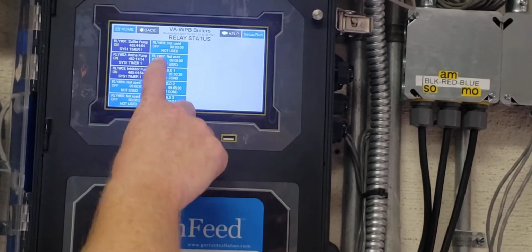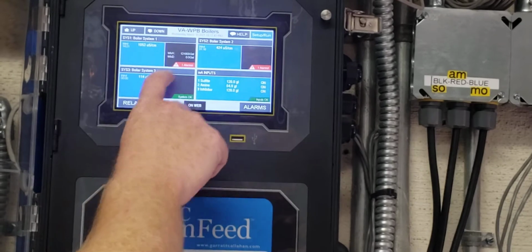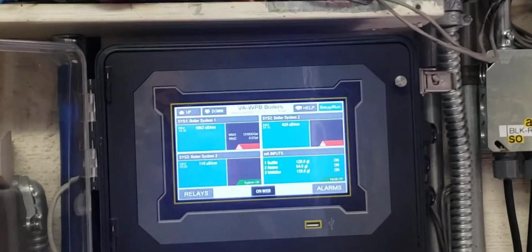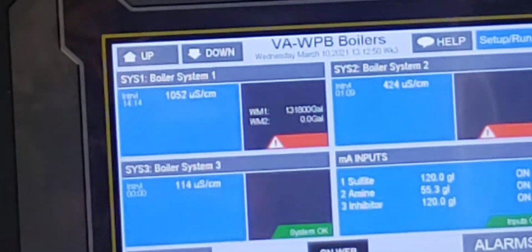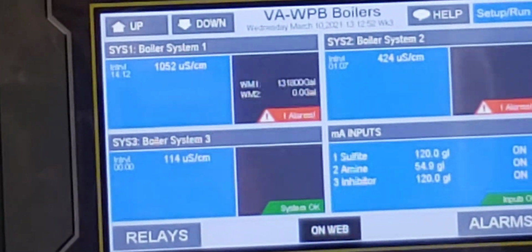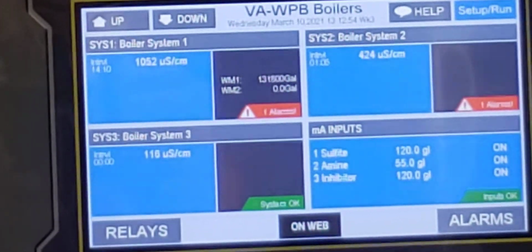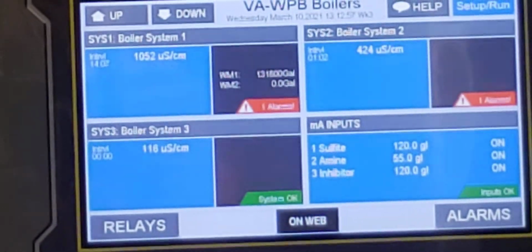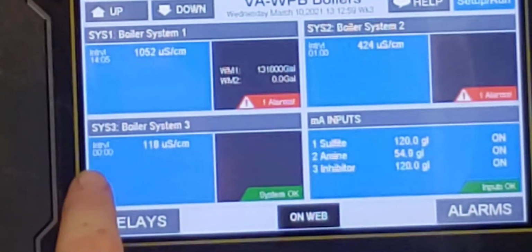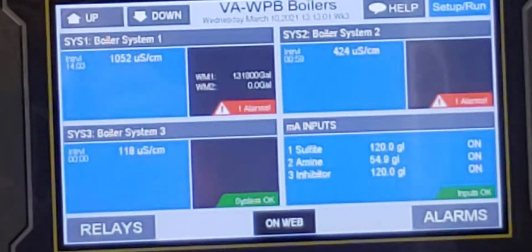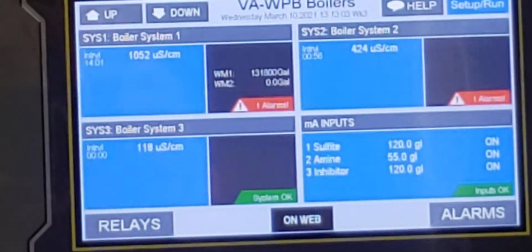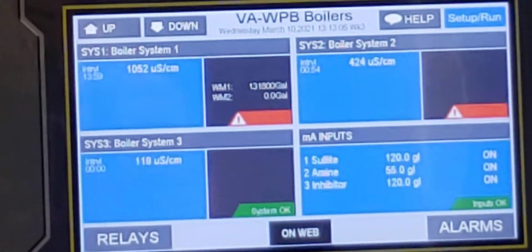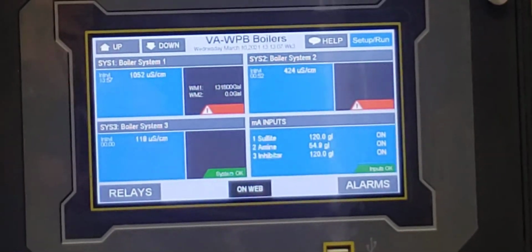Oh, so that interval countdown is up on that main screen. You want to make sure that interval is set. See, boiler 1 is in the interval stage right now, so you don't have to do that manual opening of the valve because it just did it. So it's doing the hold right now, but on this one the interval's at 0, so I know that I have to open the valve up to get a fresh relative sample to what you just took.